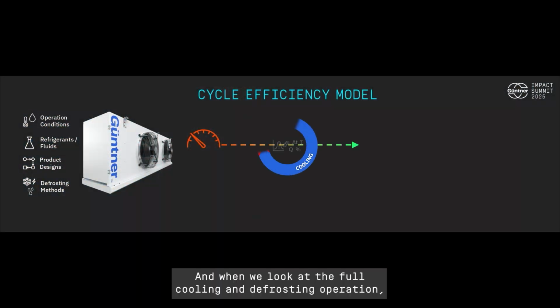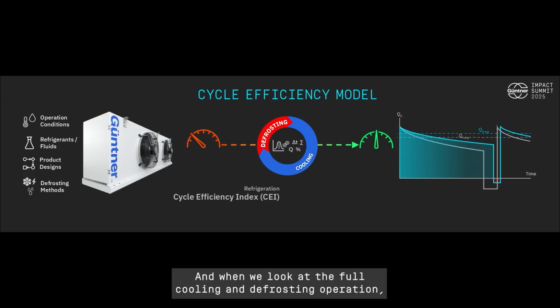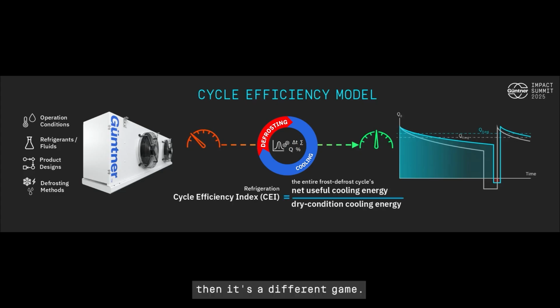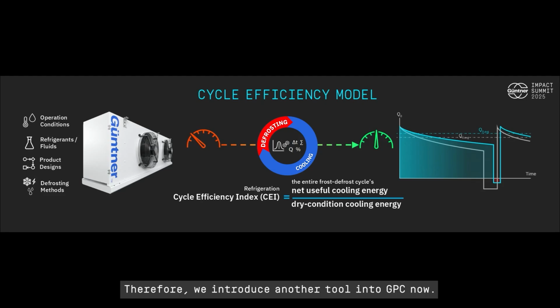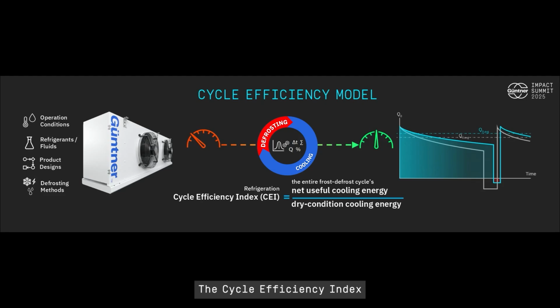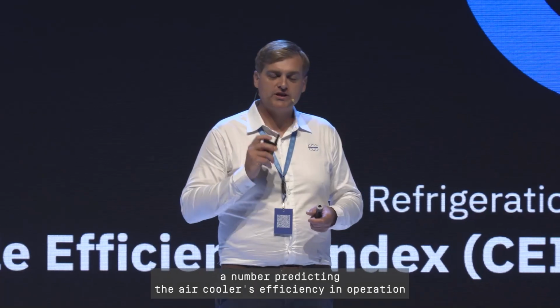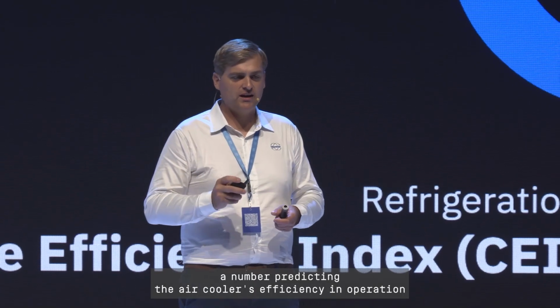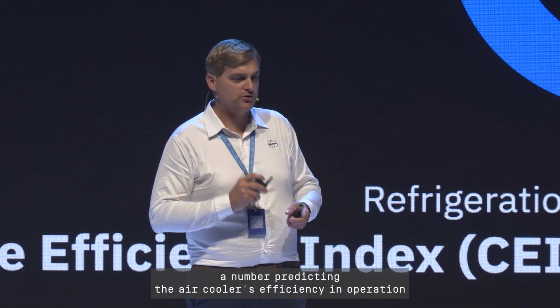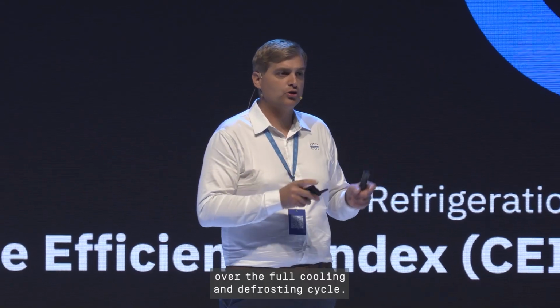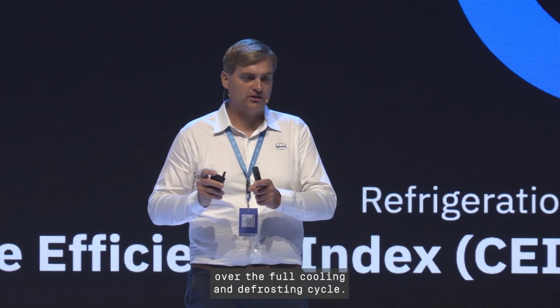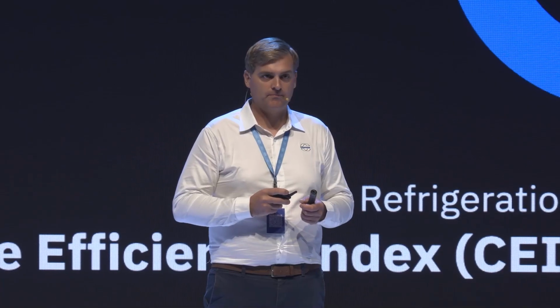And when we look at the full cooling and defrosting operation, then it's a different game. Therefore, we introduce another tool into GPC now: the Cycle Efficiency Index - a number predicting the air cooler's efficiency in operation over the full cooling and defrosting cycle.